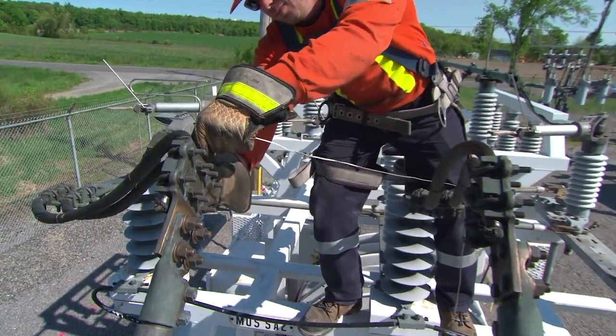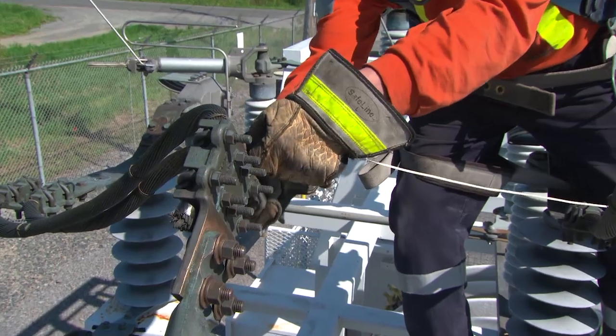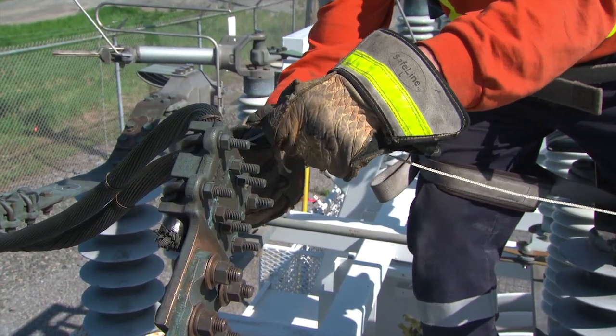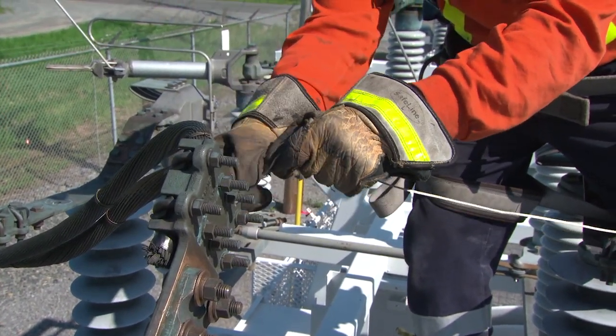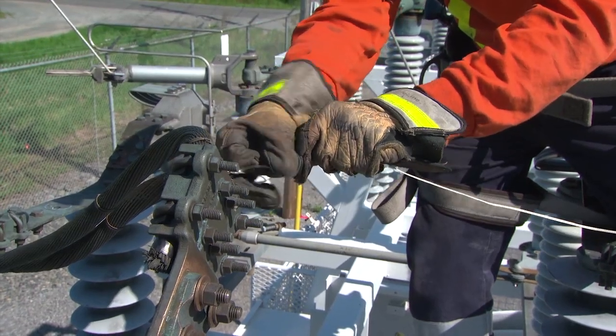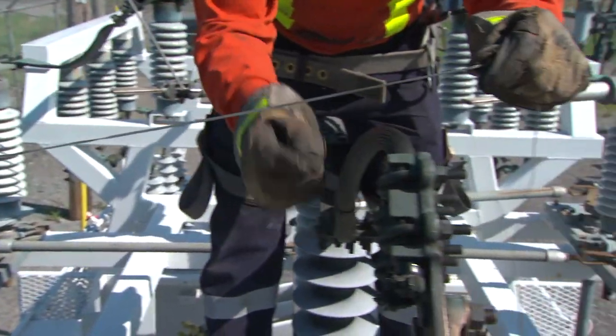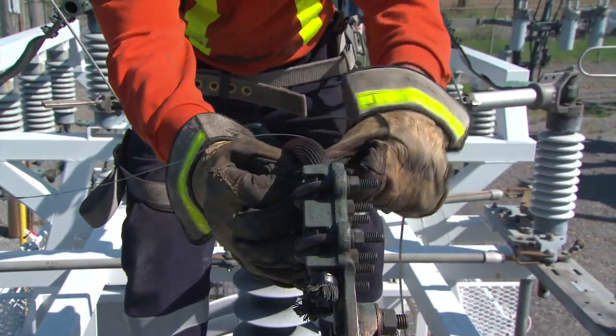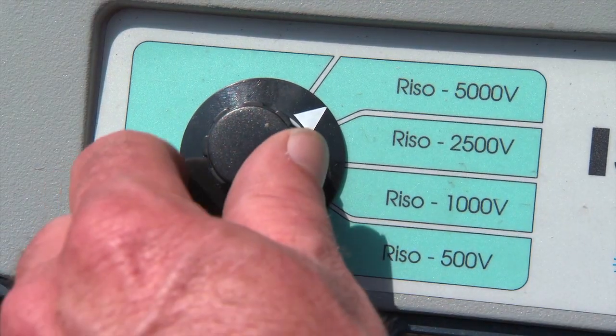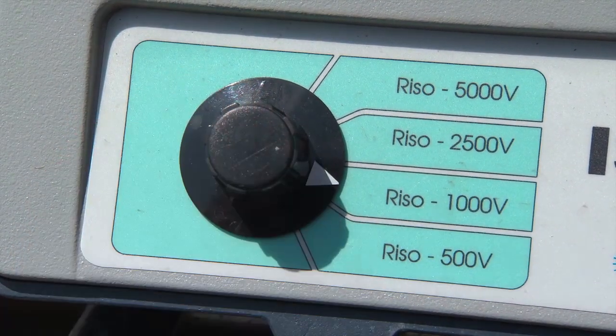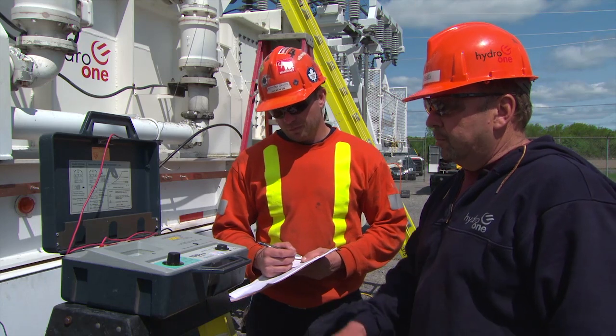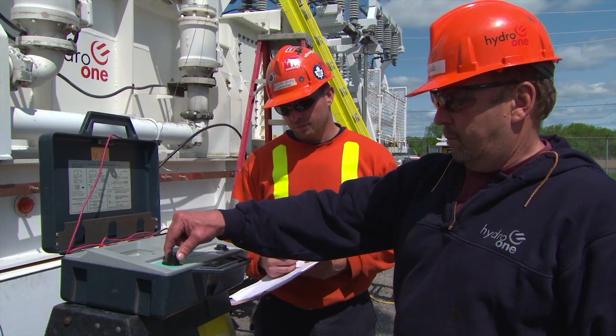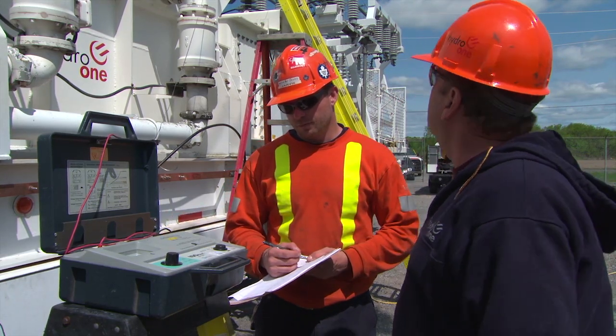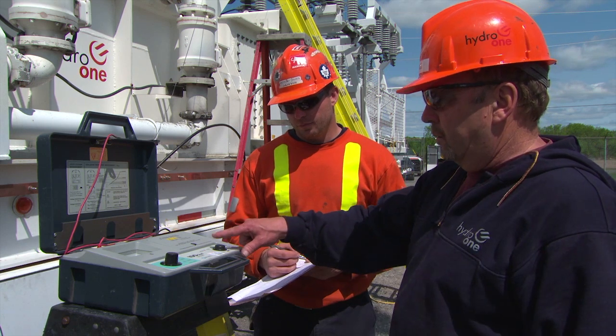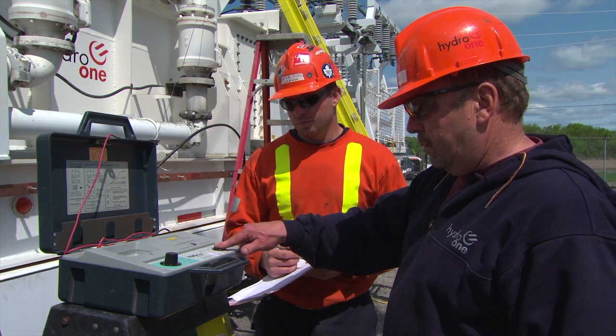For a 2-winding transformer, you must test high voltage and low voltage windings to ground, low voltage windings to grounded high voltage windings, and high voltage windings to grounded low voltage windings. Each test is performed at 1000 volts for 1 minute using a Megger tester. If you are using an electronic Megger, you may want to install a remote trigger button. This will allow you to perform the testing from a safe distance.